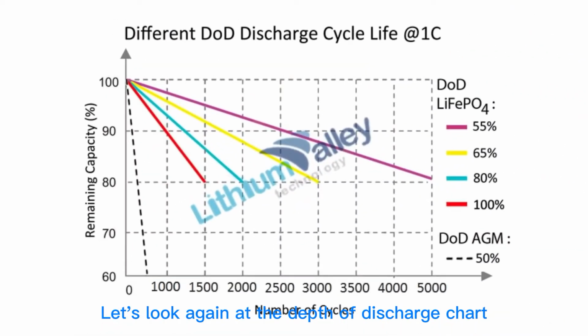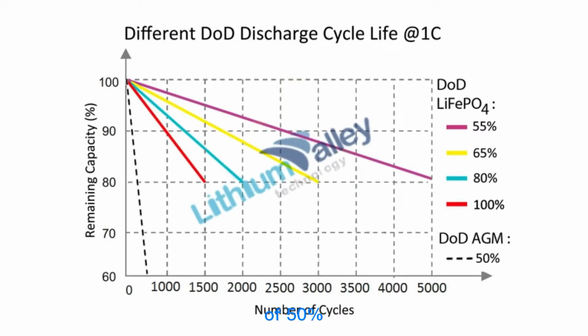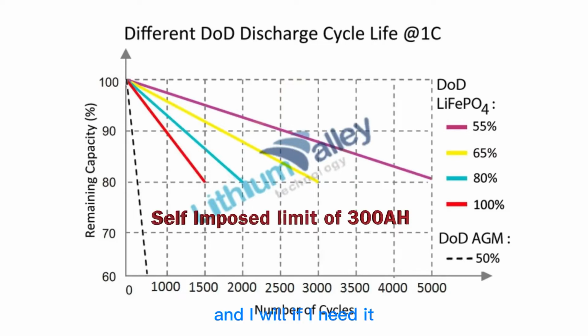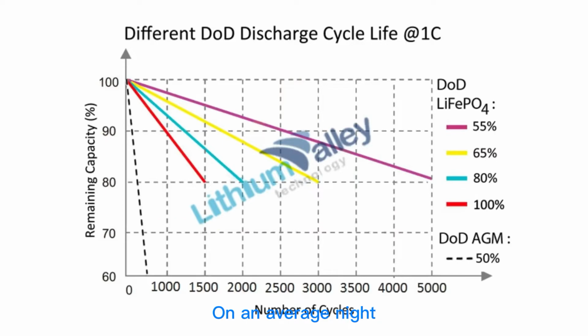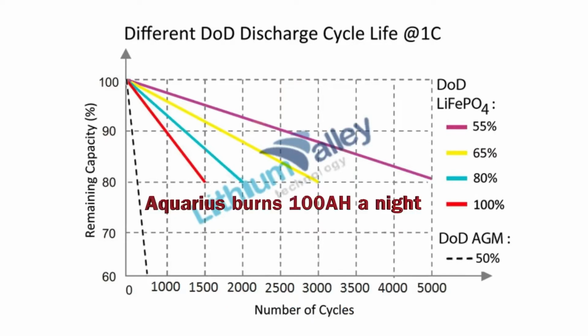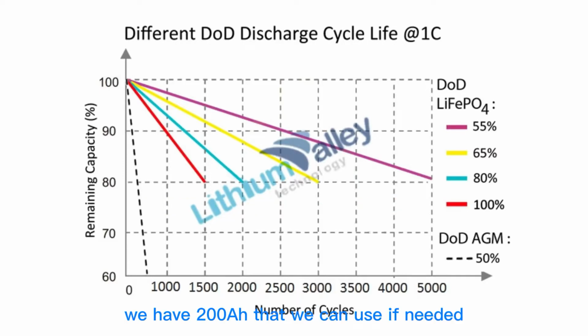Let's look again at the depth of discharge chart. In order to stay below my depth of discharge limit of 50%, I will limit my depth of discharge to 300 amp hours. Yes, I could use more, and I will if I need it, but for day-to-day operations, I will try to stay within my self-imposed limit. On an average night, between 6 p.m. and 6 a.m., Aquarius uses about 2.5 kilowatt hours, or approximately 100 amp hours of capacity. Thus, staying within our limits, we have 200 amp hours that we can use if needed.